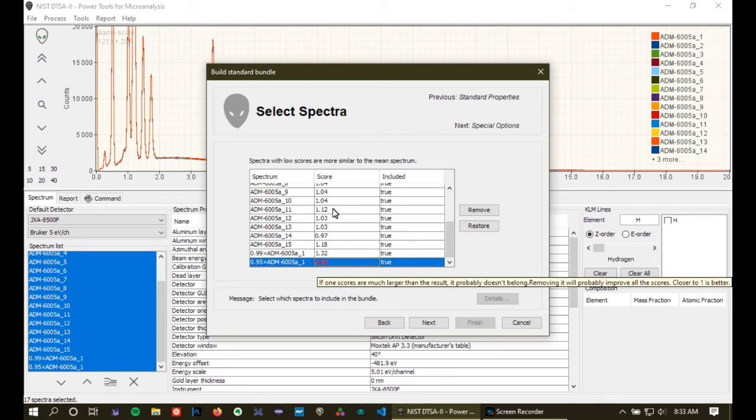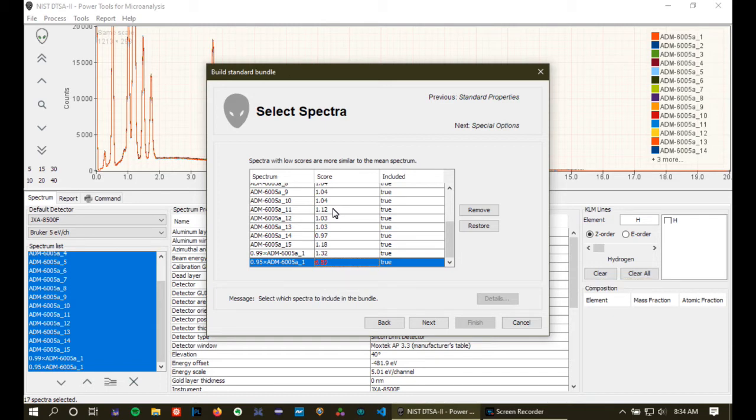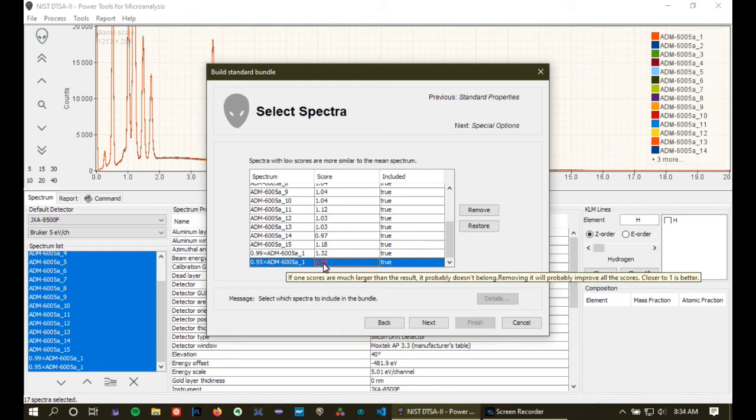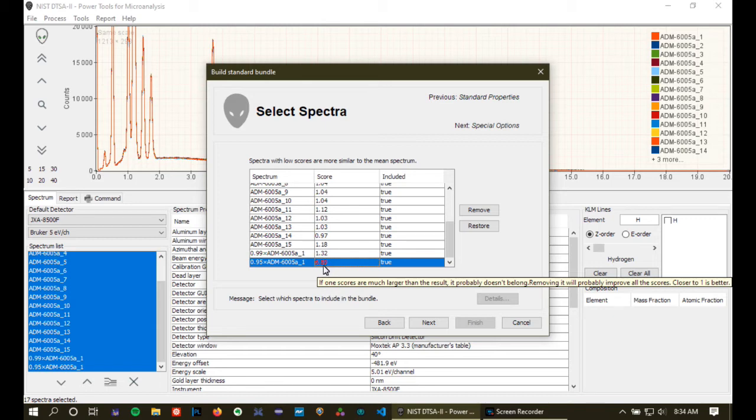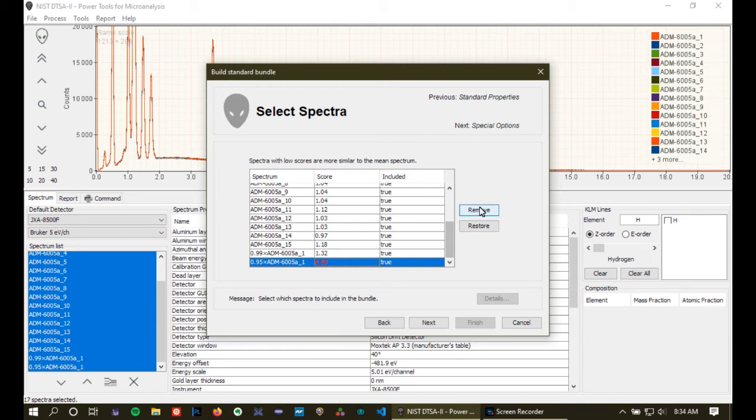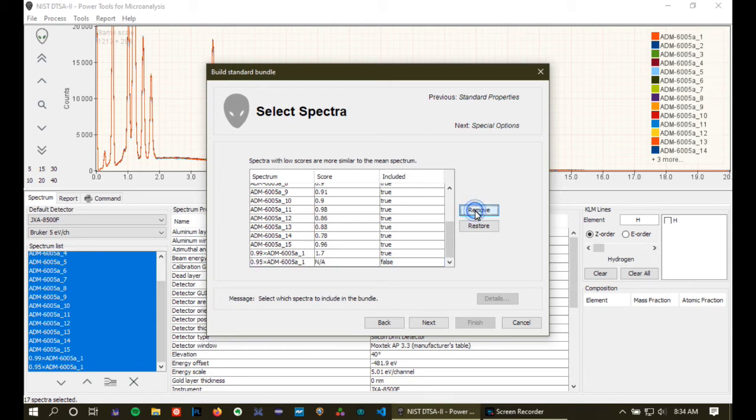For materials that are less homogeneous, like natural minerals, for example, you may never be able to collect a set of spectra that are only limited by count statistics. For those materials you just have to do the best you can and one of the advantages of averaging together many spectra is that you end up with a standard that represents some sort of mean for that material. But having said that, this material is very homogeneous, except we find this one here, the one that we actually created to be 95% the intensity, has a score that's marked in red of 6.9, where the rest of them are a little around 1.3, or a little below 1.3. So I'm going to remove that one, and you'll see it now gets tagged as false.